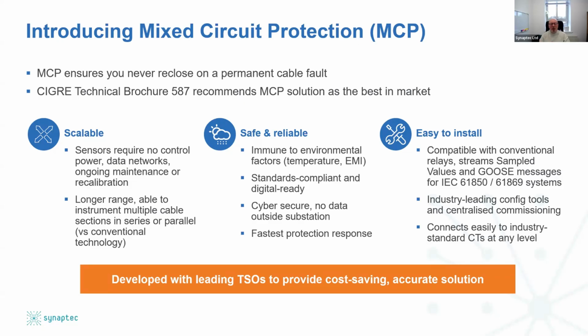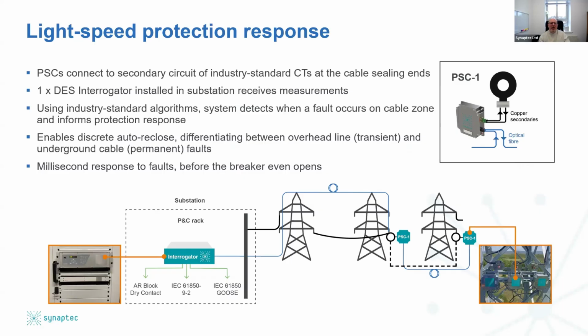And when Neil says it's cyber secure, well, there is literally no data outside the substation. There's just light going up forwards and backwards through the fiber. It's completely unhackable and unbreakable. You'll only create data at the center by those super merging units that Neil described, the interrogators. So this is a very simple way that we've developed with some leading operators to deliver that centralized protection and control function. And most mixed circuits would look something like this.